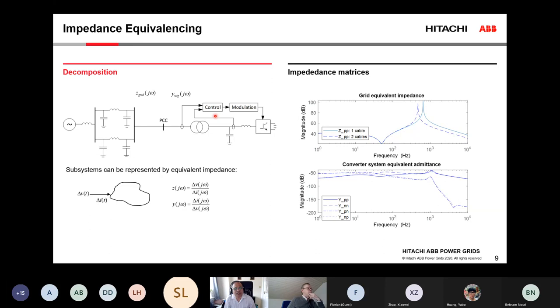Particularly, the delay has an impact on the stability margin that you also get through Nyquist or generalized Nyquist, and it can give a different margin with the same grid strength, depending on whether you consider the delay or not. That will be in the next section of the talk. How do we model this delay? You need to approximate the delays. And depending on how you do that approximation, you may predict a stable system or an unstable system. So it's very important to think about whether the models we are using are actually applicable in the frequency range we are going to use them.